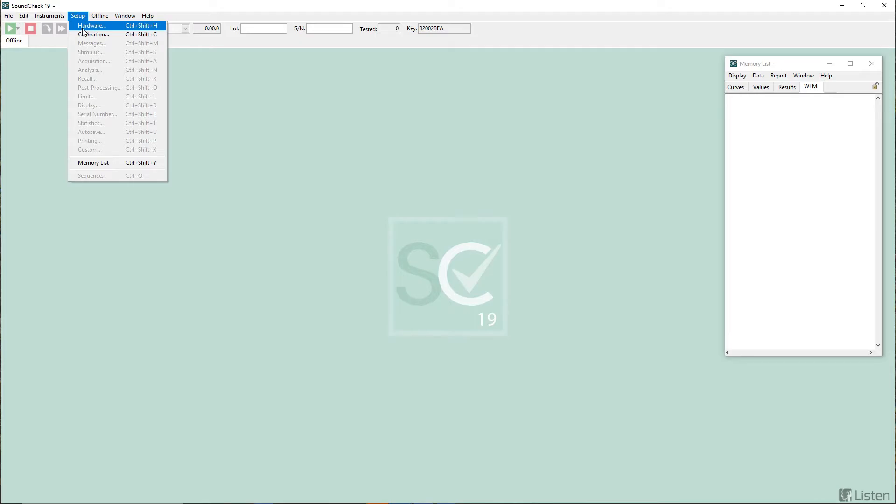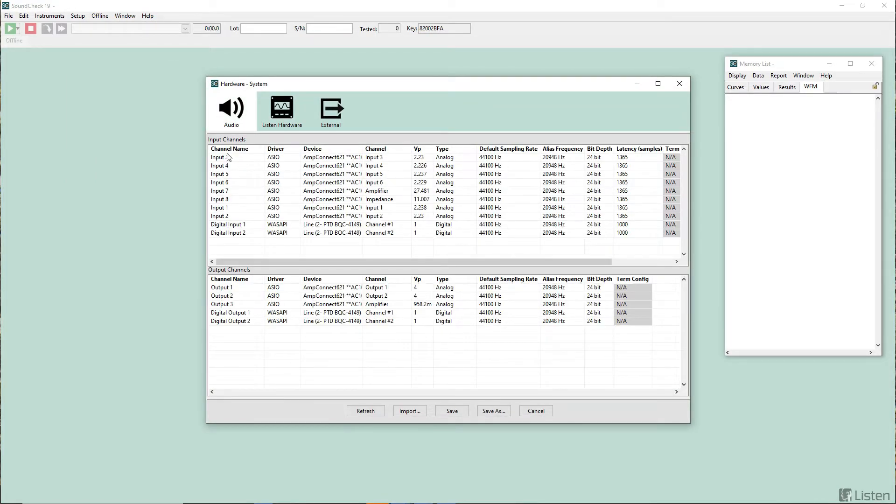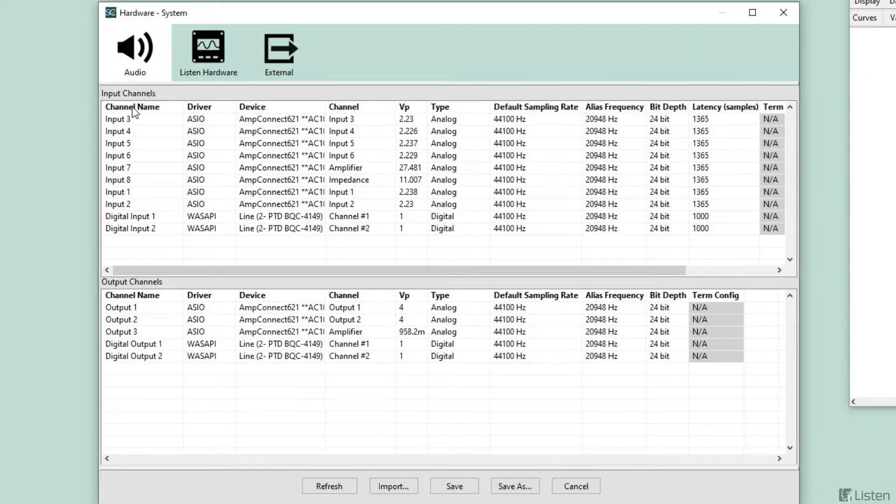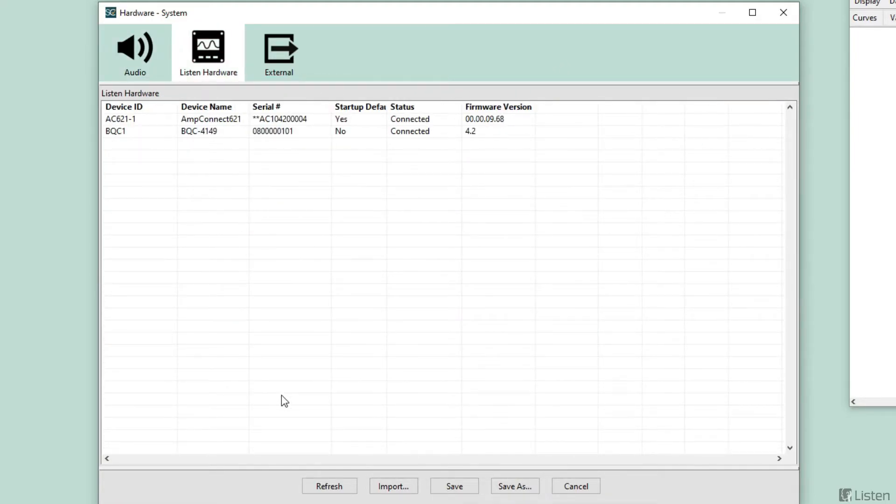Let's look at the support in Soundcheck 19. If I go to the Setup Hardware tab, you'll see I've got a 621 configured with much more inputs configured as an ASIO device. These are my input channels. I have discrete inputs for the amplifier and impedance. This is a self-calibrating interface. It's calibrated as it leaves Listen. And we could support sampling rates all the way up to 192 kilohertz.